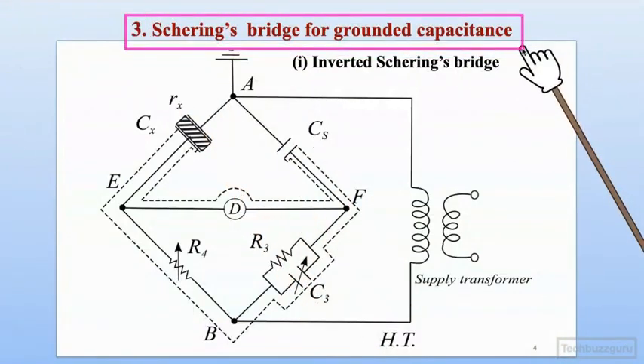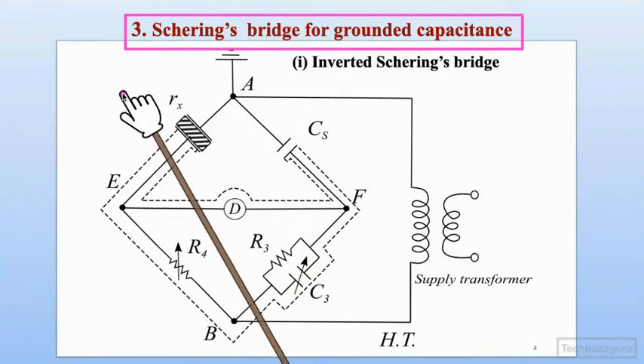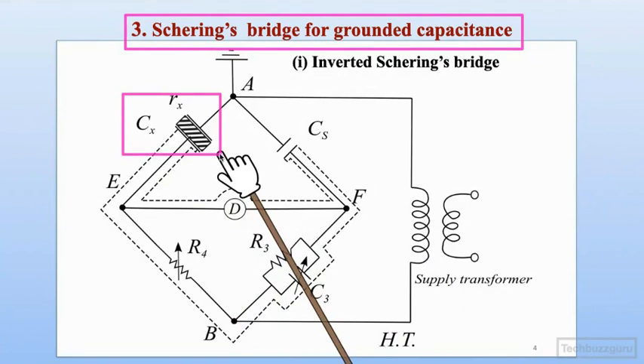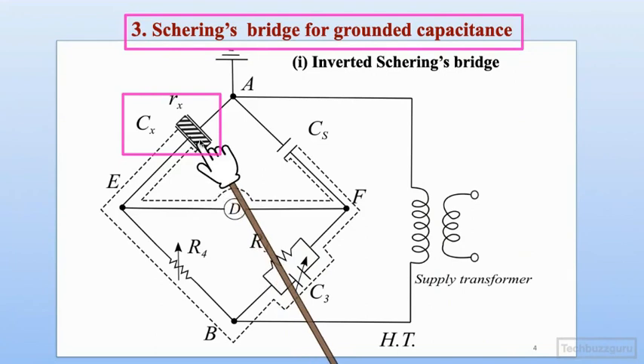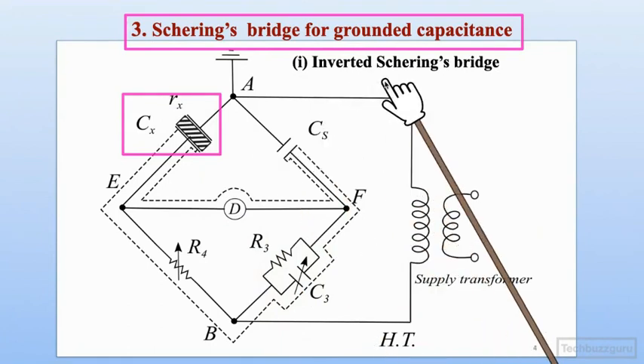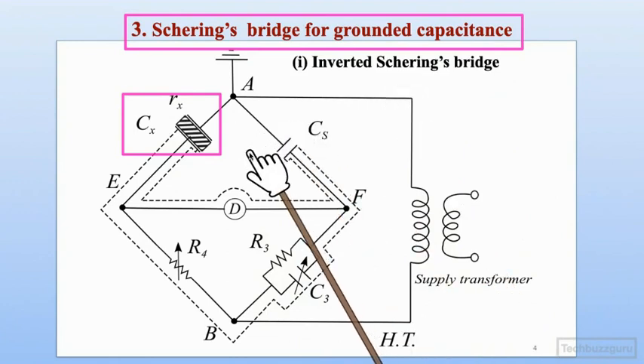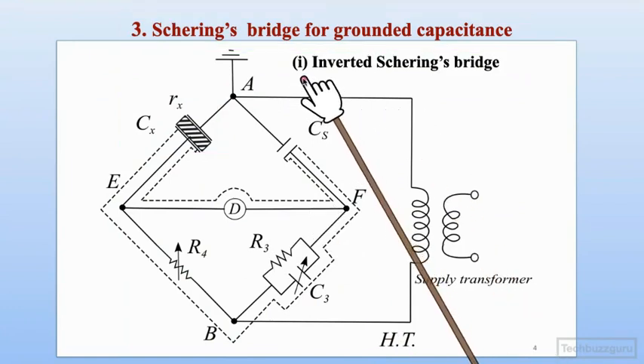The first configuration is the Schering bridge for grounded capacitance. The unknown element to be measured represents a grounded capacitance type of electrical apparatus - maybe a cable which is grounded, or a transformer bushing mounted on the transformer tank with its flanges connected to ground. Various methods are adopted to measure this kind of scenario and to minimize stray ground capacitances.